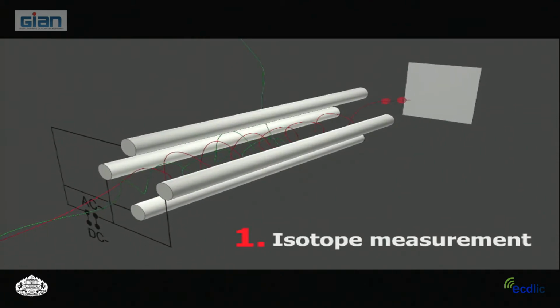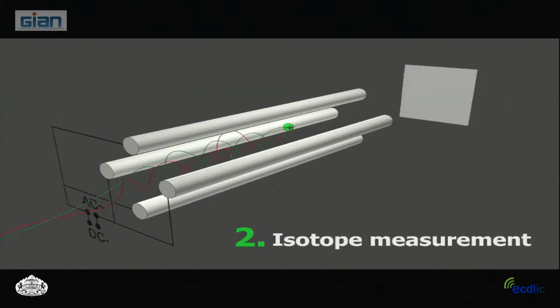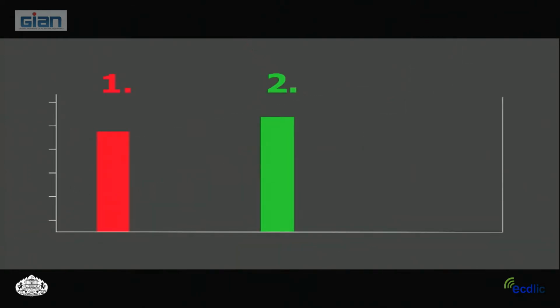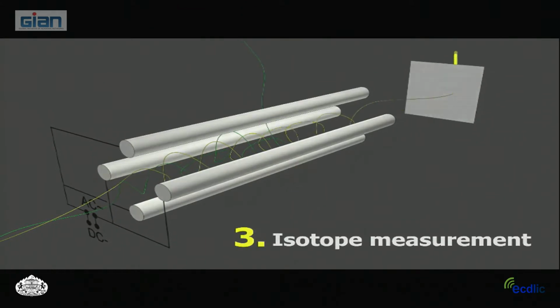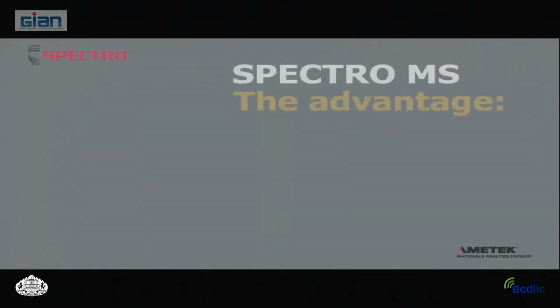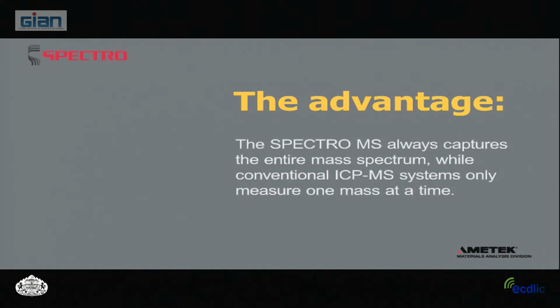That's a quadrupole. So this is the way to select from different masses, not using a magnetic sector. Using the property of vibration of the ion, you select the frequency and the tension on the quadrupole, and according to this, you can select different ions. Definitively, it's not used for isotopic measurements because it doesn't give you beautiful peaks to measure the intensity of the peak.